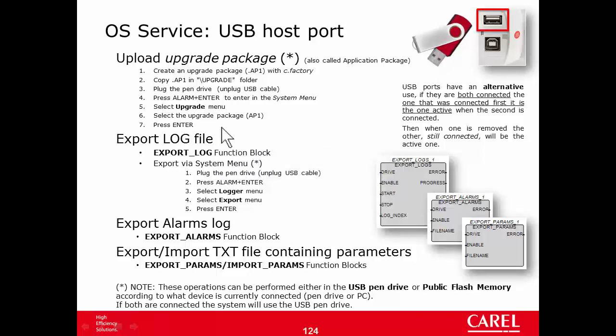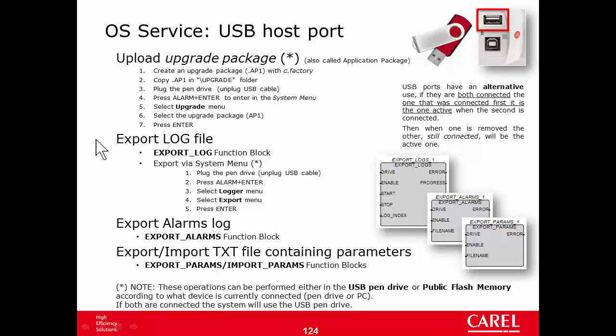With the pendrive you can upload upgrade packages (also called application packages — covered in tutorial 26). You can export logs using the export log function block, selecting the drive (USB or internal memory), the time period, and the log to export. Export is also possible using a mask in the system menu, as seen in tutorial 21.